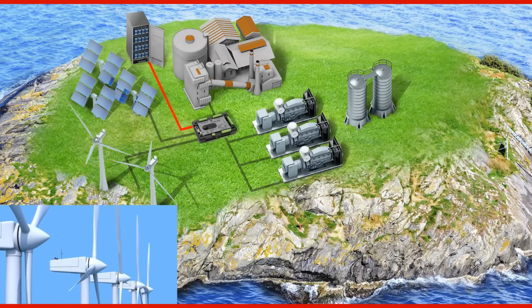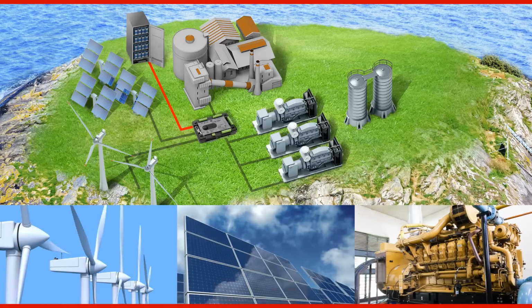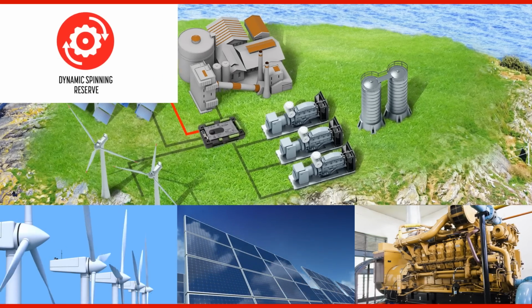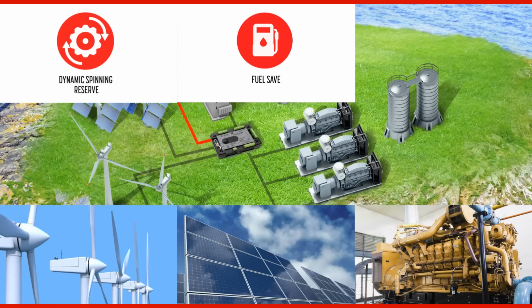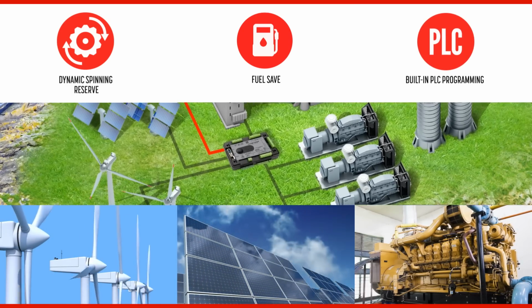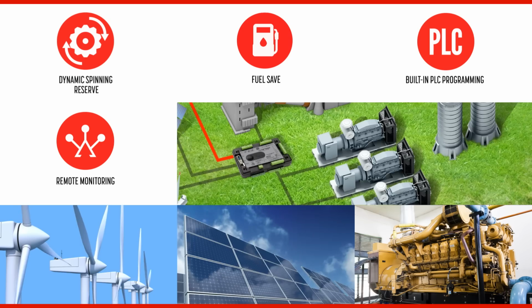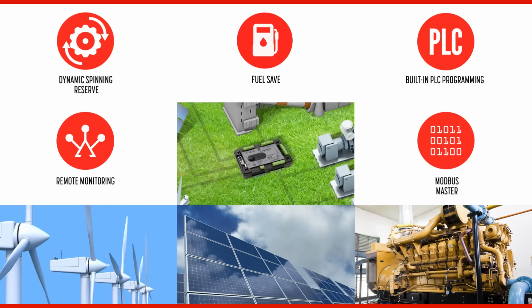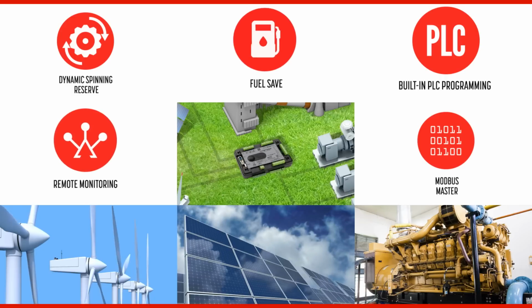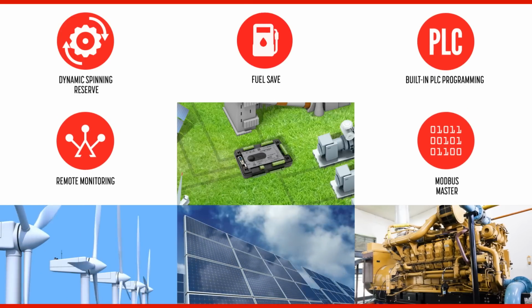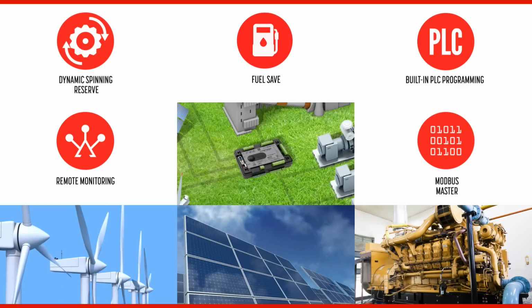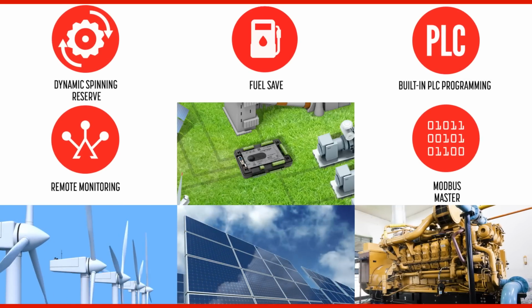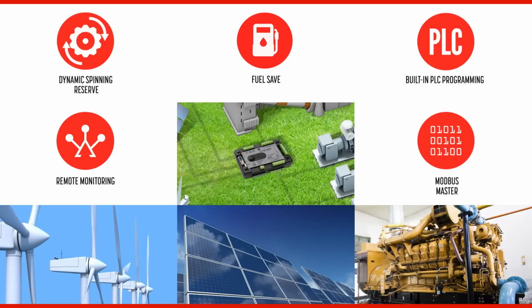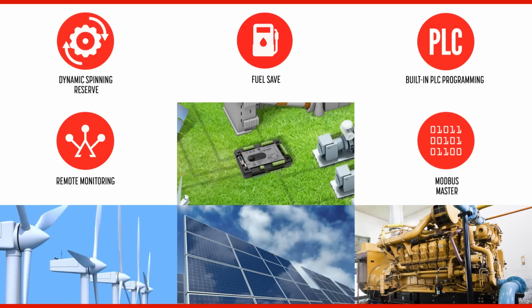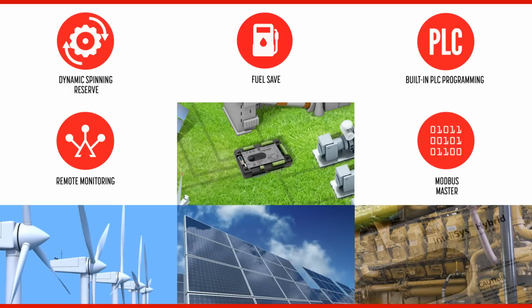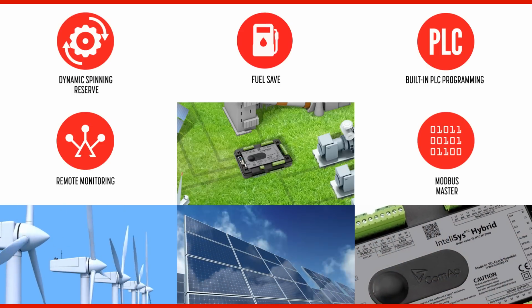The ComAp InteliSys Hybrid contains a function called Dynamic Spinning Reserve. This function changes the amount of generators running according to the amount of power produced by the renewables to ensure the system can cover a drop in renewable input to the system. The ComAp InteliSys Hybrid controller can manage outputs from generators of different sizes, power outputs, and from different manufacturers. The fuel save mode in the controller will automatically choose the most efficient combination of generators to save extra fuel, even out maintenance schedules, and reduce wear on the generators.